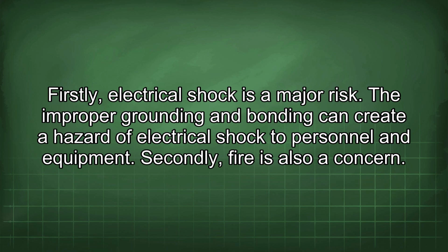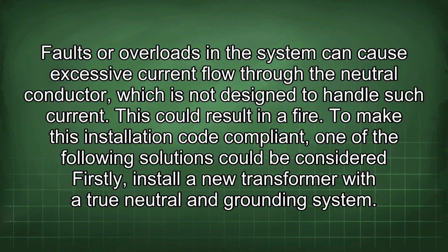Firstly, electrical shock is a major risk. The improper grounding and bonding can create a hazard of electrical shock to personnel and equipment. Secondly, fire is also a concern. Faults or overloads in the system can cause excessive current flow through the neutral conductor, which is not designed to handle such current. This could result in a fire.